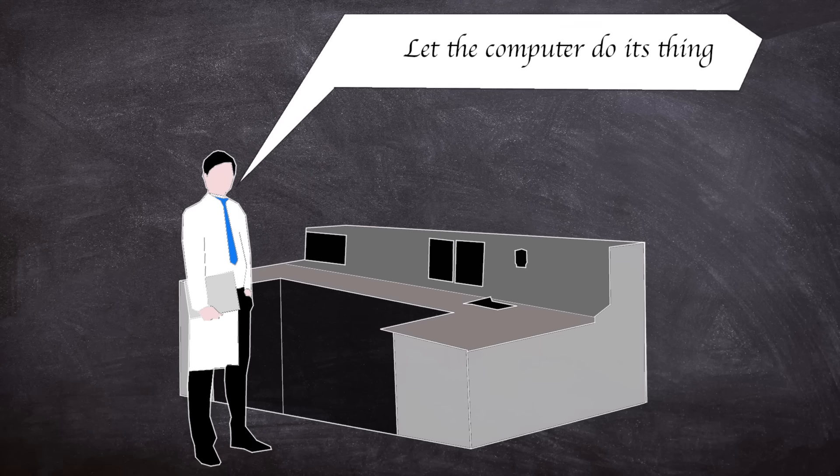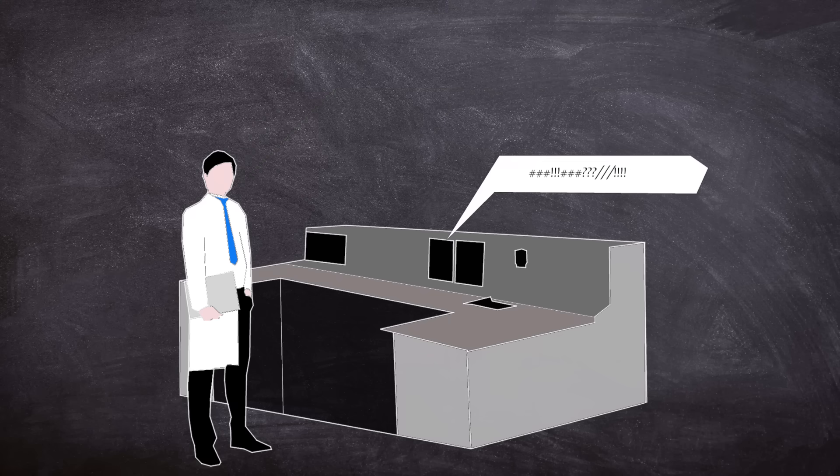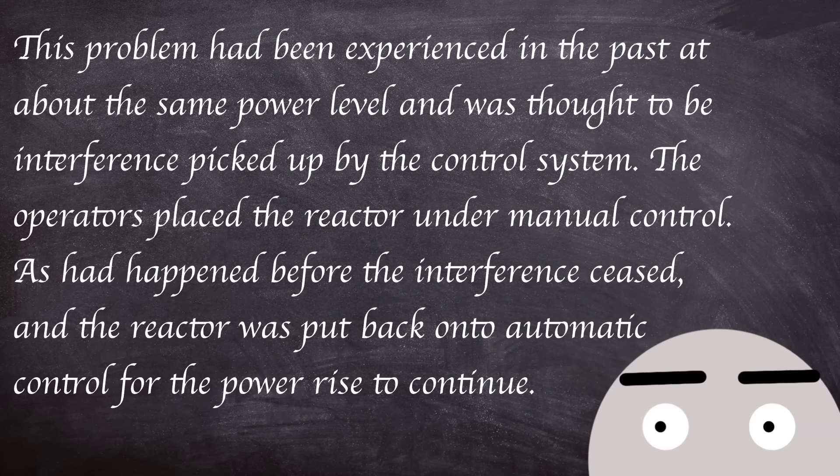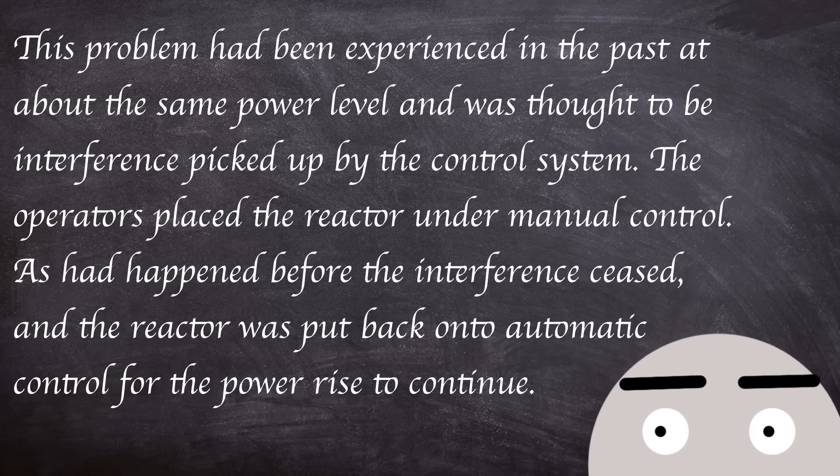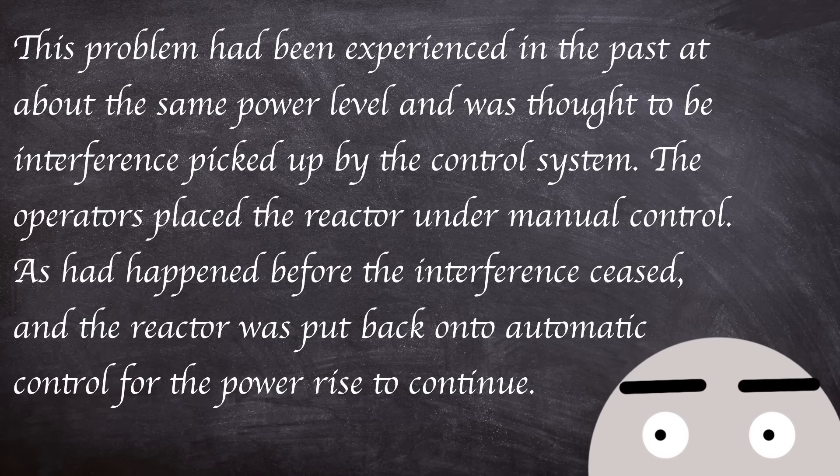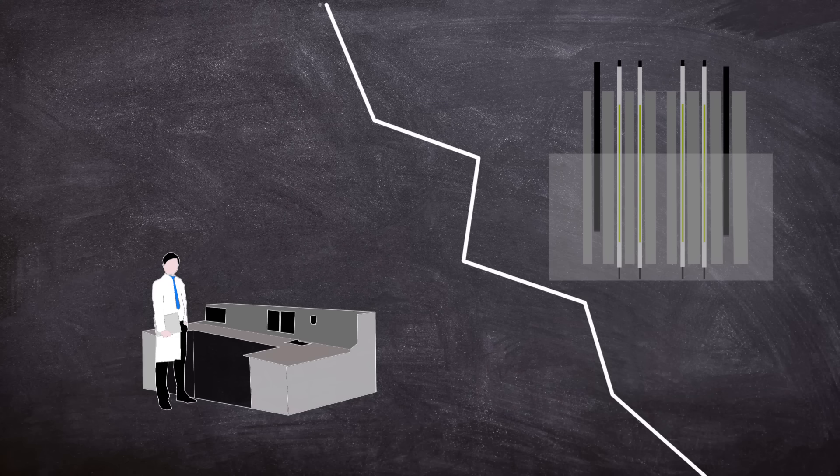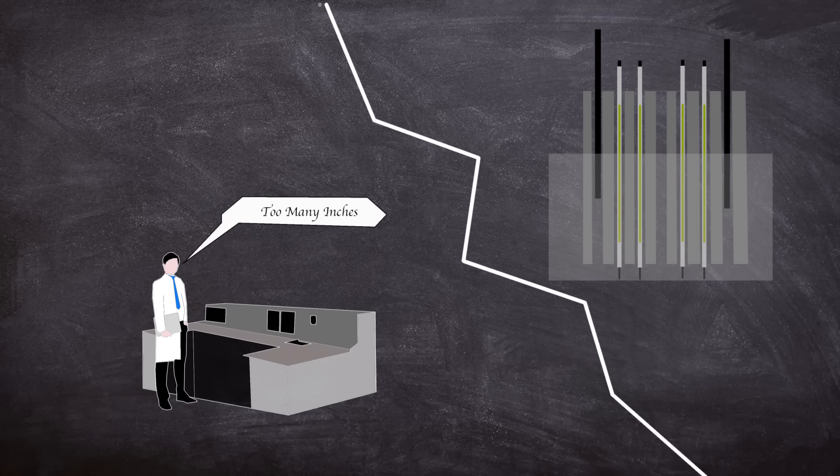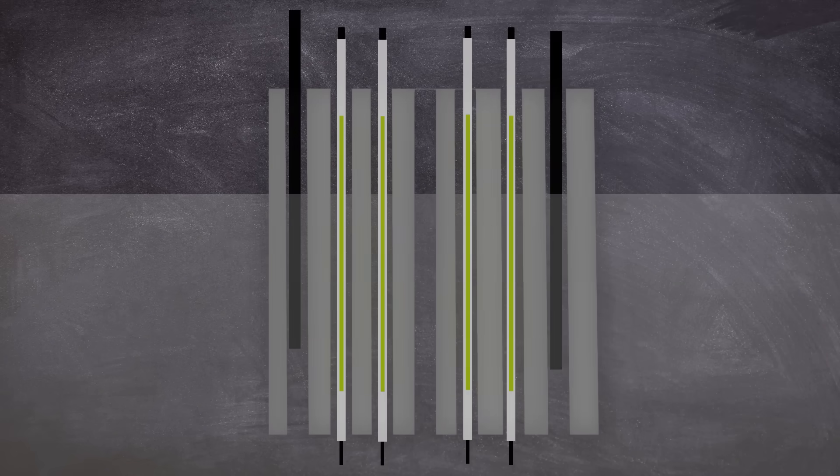The reactor was then put on automatic control until about 3 PM, reaching a power of 20 megawatts. The reactor operators observed variations in the automatic control system. This problem had been experienced in the past at about the same power level and was thought to be interference picked up by the control system. The operators placed the reactor under manual control. As had happened before, the interference ceased and the reactor was put back onto automatic control for the power rise to continue. Just after 3 PM, a staff member in charge of the operation saw that the control rods appeared to be withdrawn further than normal for this power level. Both the shim and regulating rods were approximately 9 inches withdrawn—usually at this time the rods would be at around 6 inches. Abnormally high sodium outlet temperatures were being indicated over two sub-assemblies.